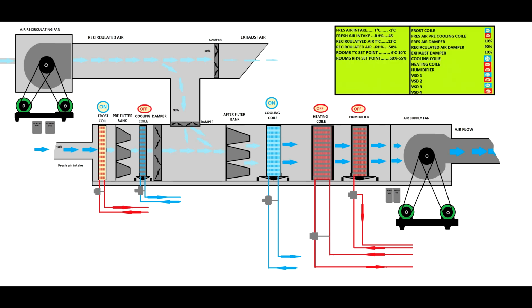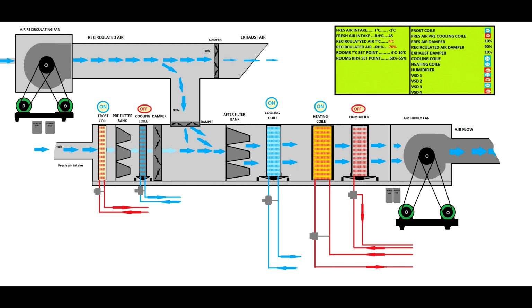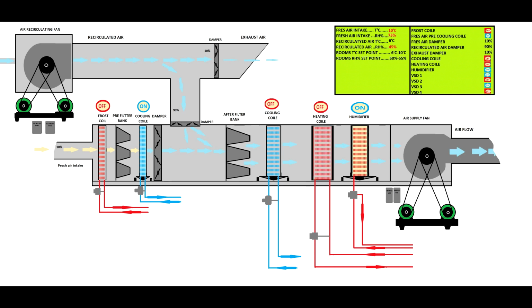And what you will see now here, all these lights are changing. Every single heat exchanger is activated or deactivated. The PLC is constantly monitoring the air quality, applying that data against the software and controlling the actuators to have a constant airflow, temperature, and relative humidity. A human being cannot do that. That's an illusion.